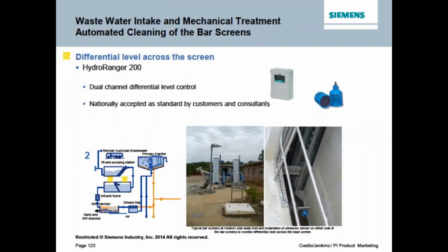We talked about this one already, so I'm not going to spend a ton of time here, but bar screens or mechanical screens doing the differential across. It's really nice for an ultrasonic because we have a dual channel transmitter that'll talk to 2 transducers and do that math or that differential for you. It can even do an average across, depending upon what it is that you want to see. And we give you relay outputs to do any sort of control function based off of some differential level.